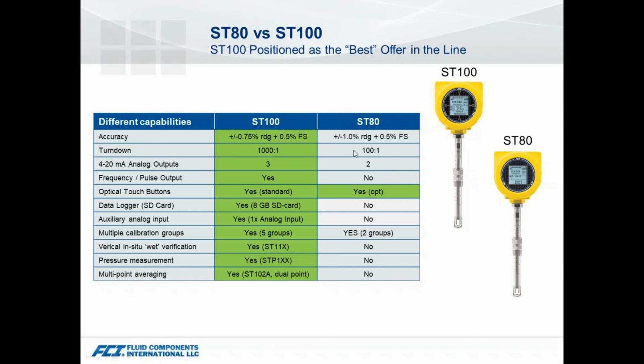This is kind of a typo, but instead of a 200 to 1 turn down, we can actually do 1,000 to 1. Talked about the analog outputs, the touch buttons. One area we have, it also has an onboard data logging system. So with an SD card, you can store readings if the meter's set up for it through the software. Do up to 5 calibration groups. This comes into play a lot of times with your flare gas applications.